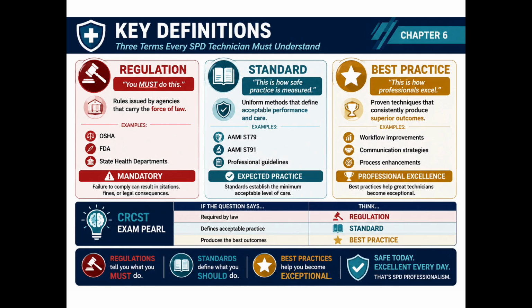Best practice. Our text defines best practice as a method or technique that has consistently shown results superior to those achieved by other means. A best practice is the most effective and proven way to perform a task safely and correctly. It's based on research, experience, and professional standards that show what consistently produces the best results for patients and staff. In sterile processing, best practices are the methods that ensure instruments are clean, sterile, and ready for use every time. Here's an example. Using a type 5 chemical indicator inside every sterilization load is considered a best practice because it reacts to all critical parameters, giving a reliable confirmation that the cycle met sterilization conditions.